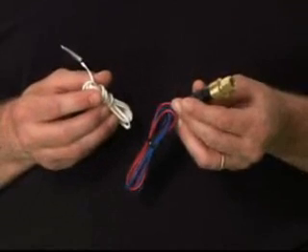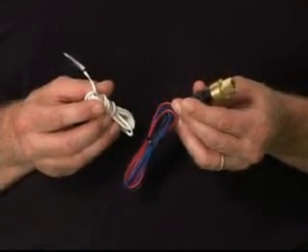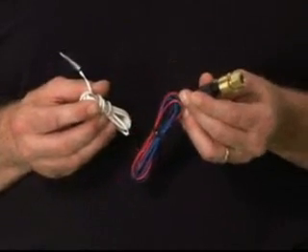The control can monitor system status either through a temperature probe in the condenser or, in some models, a transducer that tracks system pressure. The temperature probe is easy to install but takes several seconds to react to temperature changes. A pressure transducer is more accurate and responsive, but if there's no Schrader valve, you'll need to evacuate the system to install it. Of course, that's not an issue for OEM installations since the system hasn't been charged yet.